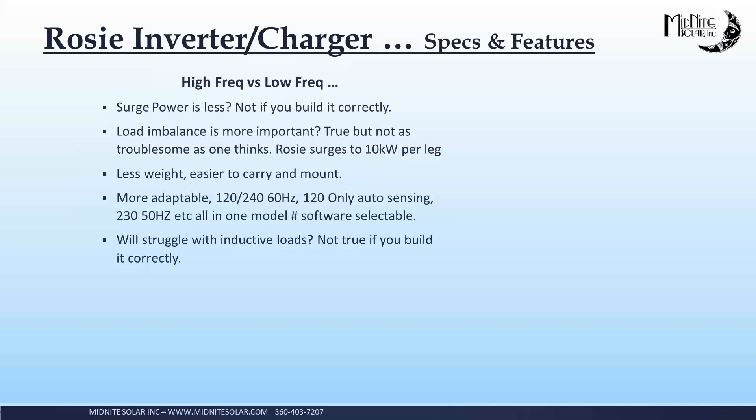Probably one of the big plusses of high frequency is less weight. Anybody who has lifted a Schneider XW Pro or a Sunny Island knows what I'm talking about. This Rosie is seven kilowatts and weighs 42 pounds. This thing is just easy to lug and easy to mount — it's not going to break your back to get it on the wall. The other advantage of high frequency is adaptability. You can have a single inverter like a Rosie that can do 120/240, 60 hertz, 120 only auto-sensing, 230/50 hertz with the push of a button, or even auto detect 208 three-phase. The 120-volt auto sensing is pretty cool. If you've got an RV with a 50-amp service entrance — split phase 240 going in — and you take a 30-amp dog bone, the 30-amp service in the campground is 120 only. The dog bone takes L1 from the 30-amp 120 and ties it to both L1 and L2 on your 50-amp plug, and the Rosie on the mobile version will auto sense that and switch to 120-only mode and charge off both legs.